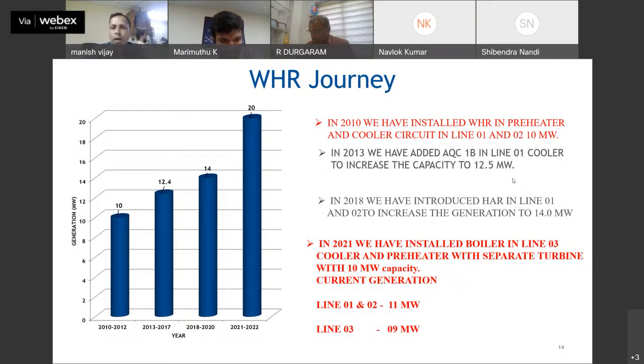We have installed WHR in preheater and cooler in all the 3 lines with 5 boilers, and the generation capacity was 10 megawatt. To further increase the power generation, during the capacity upgradation of our line 1, we installed 1 additional boiler, and the capacity increased up to 12.5 megawatt. For further increase in green power generation, in 2018, we introduced a hot air circulation system and increased the power generation up to 14 megawatt. Recently, we have installed a new boiler in the cooler and preheater of line 3 with a capacity of 10 megawatt. And current generation is line 1 and line 2 at 11 megawatt, and line 3 at 9 megawatt.